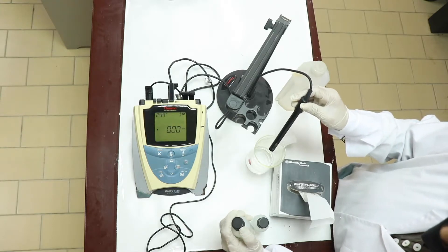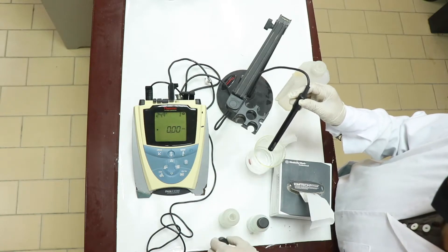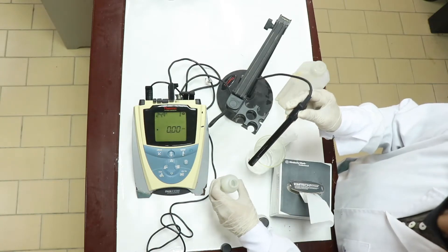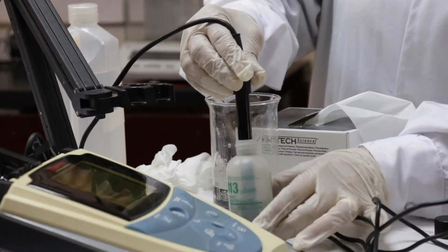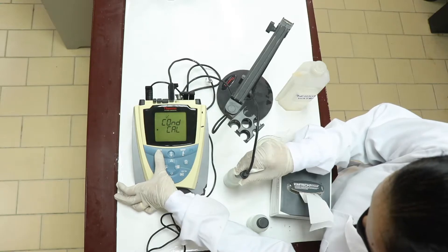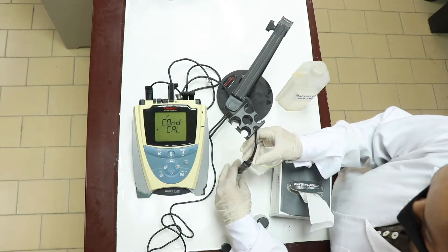Open the 1413 bottle. This solution's conductivity we already know. Now, dip this glass electrode into the solution and you have to press calibrate. Look at the screen. What is appearing? Conductivity calibration.